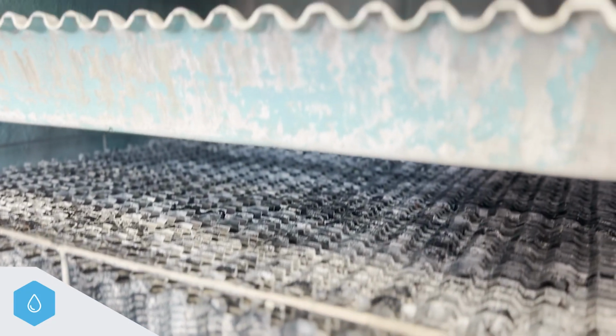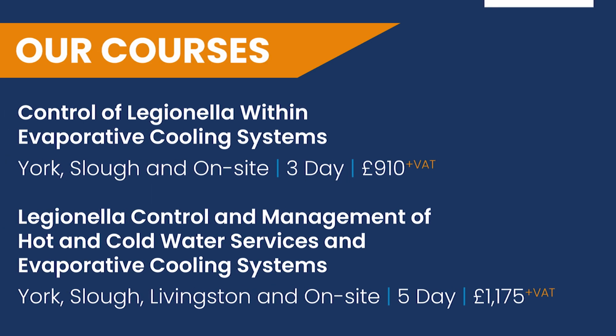And as you've seen from the state of the cooling tower, it's been mismanaged, and because of that, we've got lots of scale, we possibly have got a lot of biofilm and microbiological growth, so it's important that we manage it correctly.